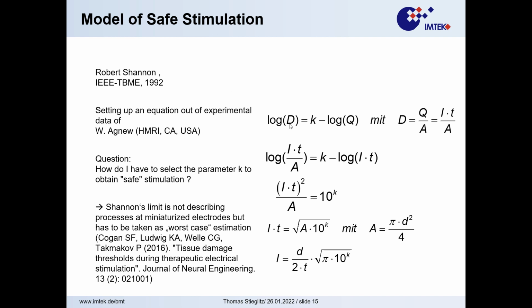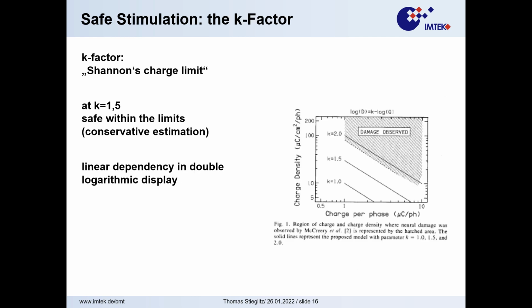But the thing is, if you take a double logarithmic display, you can assign the charge density to the charge with a linear factor. And this is then the safety margin. You can rearrange that and find out that there's a certain dependency, if you take a round electrode, on that factor. And the K factor is the safety margin. And to be at a good distance from that, you should take the K factor at 1.5. That's completely heuristic. There's no scientific reason behind that. It's just arranging data and trying to get an equation out of those data that helps us.